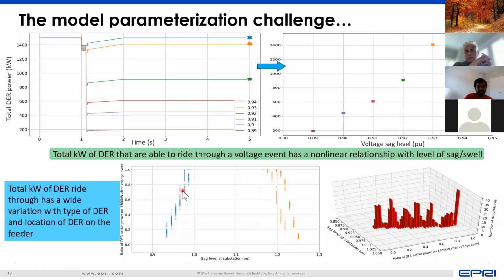What this means is, if you consider this vertical line here, depending upon how the DER is spread out across the feeder, a voltage level of 0.98 per unit can result in either 60% of the DER tripping, or no DER tripping. So there's this wide variation in how this DER would behave for a transmission level event. And this is the core of the parameterization challenge that we want to address: given the amount of uncertainty, how do we bring that uncertainty to a transmission planner and give them a best guess estimate?